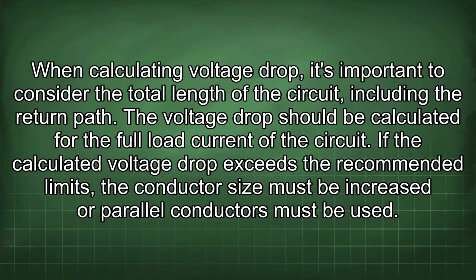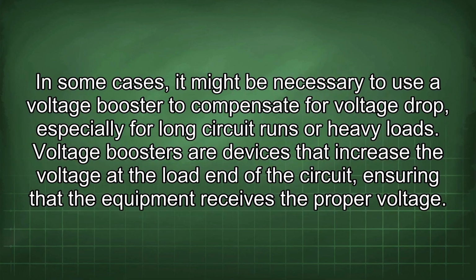When calculating voltage drop, it's important to consider the total length of the circuit, including the return path. The voltage drop should be calculated for the full load current of the circuit. If the calculated voltage drop exceeds the recommended limits, the conductor size must be increased or parallel conductors must be used. In some cases, it might be necessary to use a voltage booster to compensate for voltage drop, especially for long circuit runs or heavy loads. Voltage boosters are devices that increase the voltage at the load end of the circuit, ensuring that the equipment receives the proper voltage.